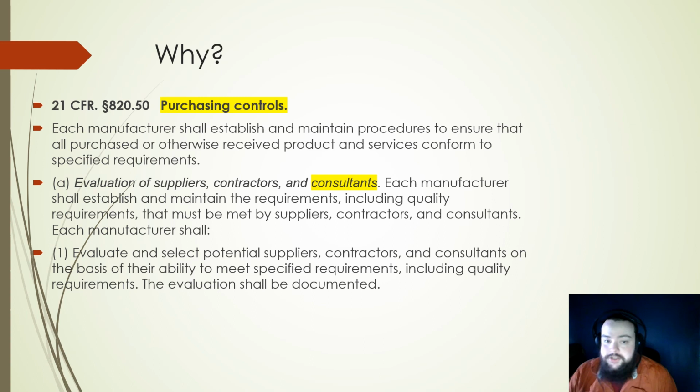And if you're going to control your suppliers as an outside resource, you might as well control them as purchasing controls through 21 CFR Section 820.50. Section A includes consultants, again, that they are managed as suppliers, even though it's not a physical thing they're supplying, it's a service that they're supplying. That should be controlled and qualified as well. You might not be in the United States market yet, but it's something to consider if you're hoping to expand there.